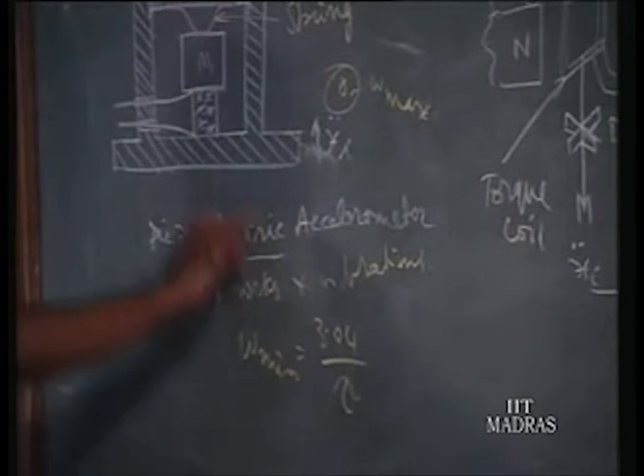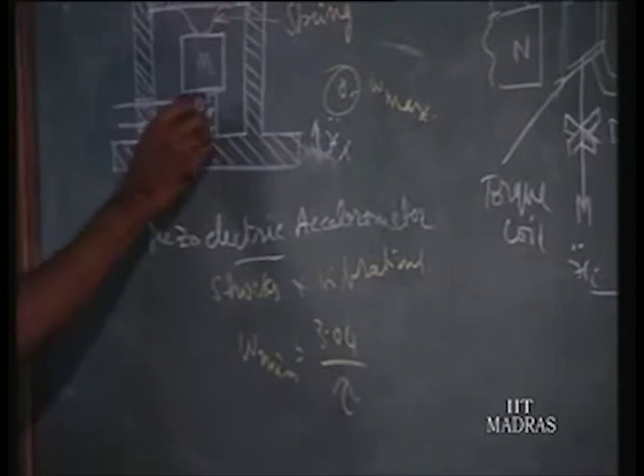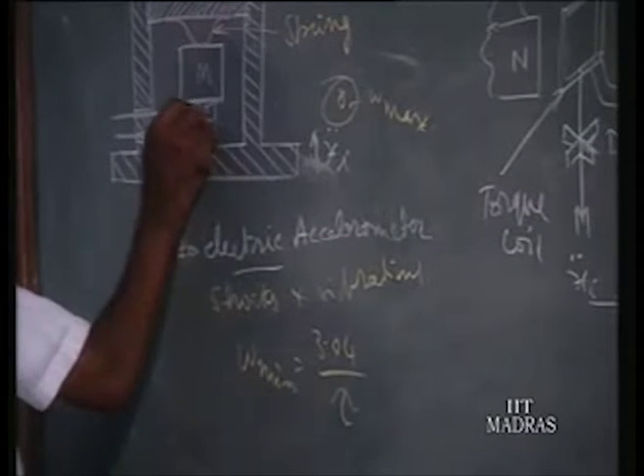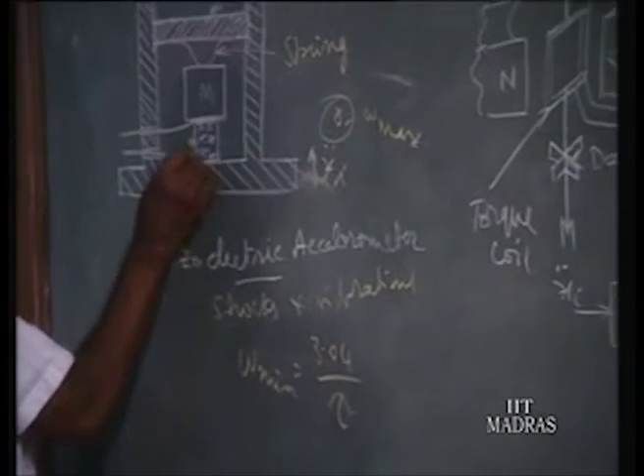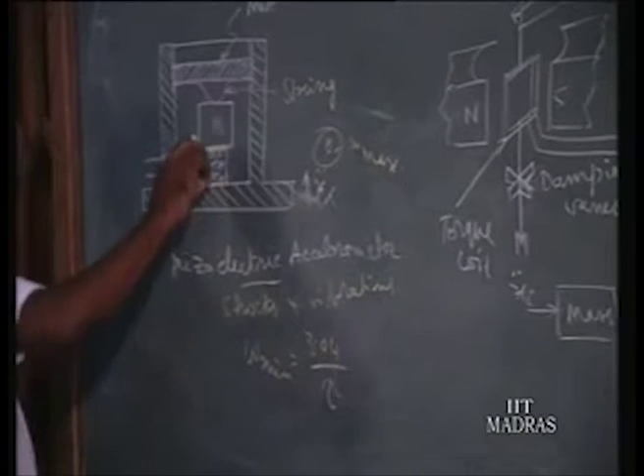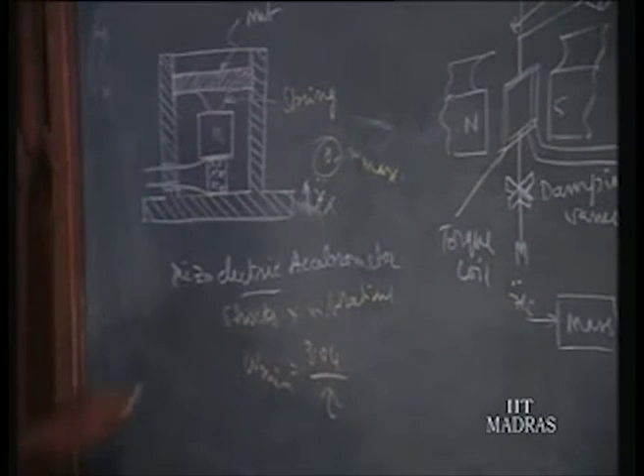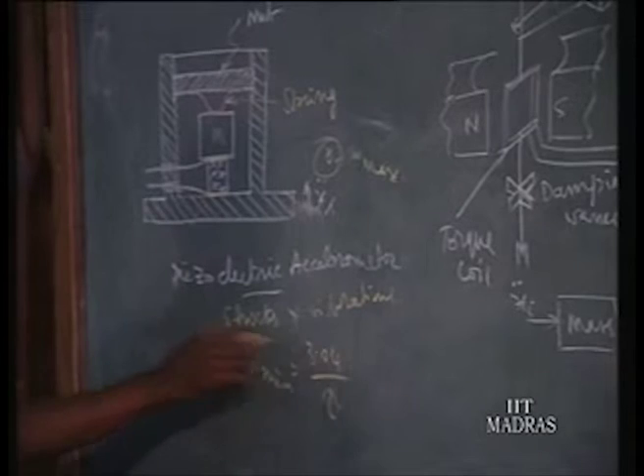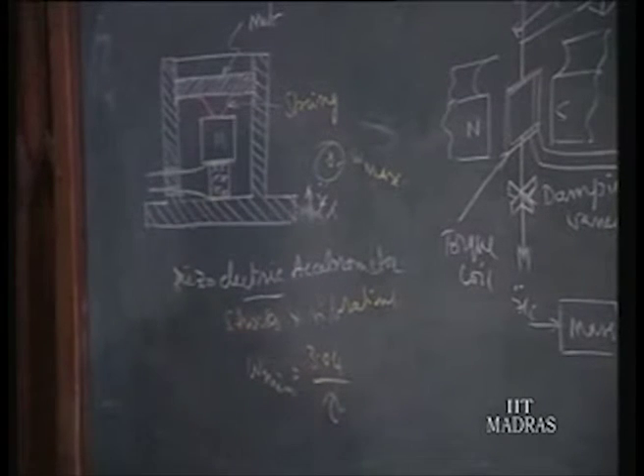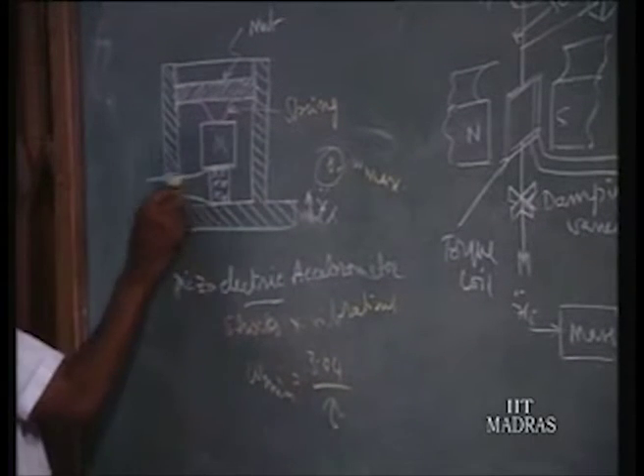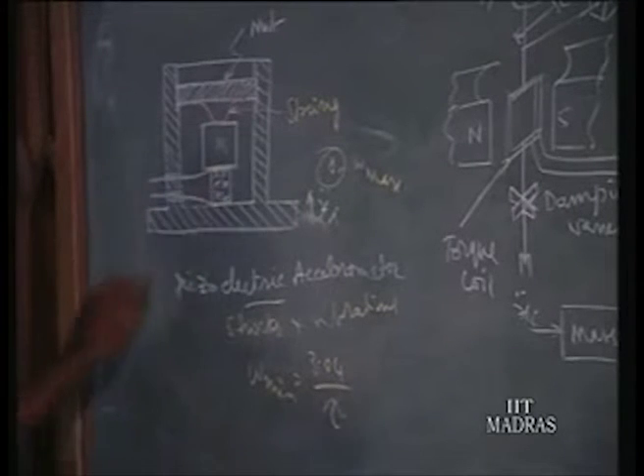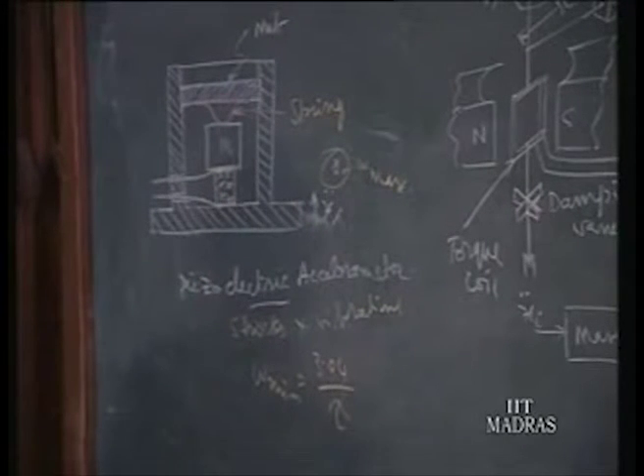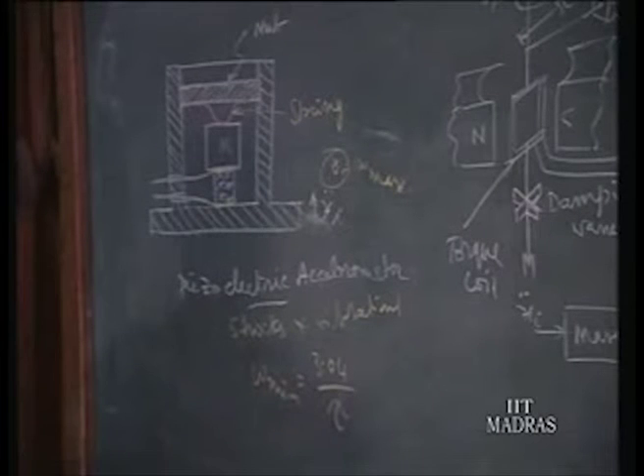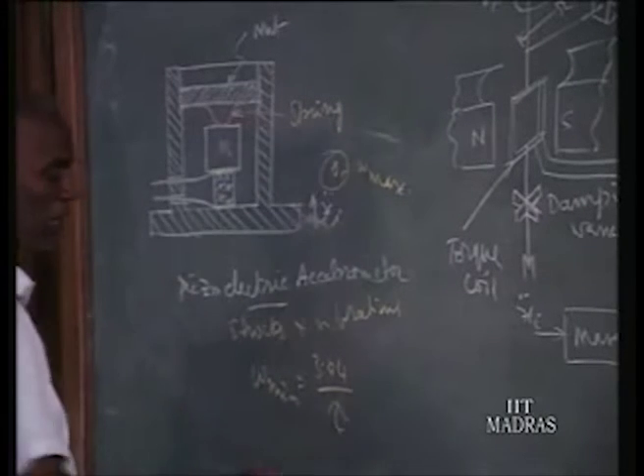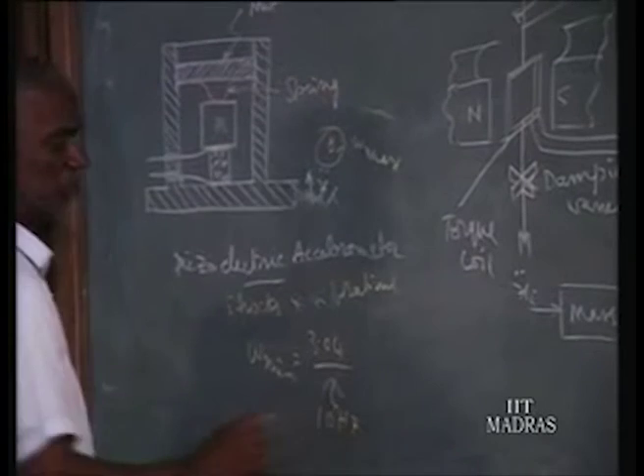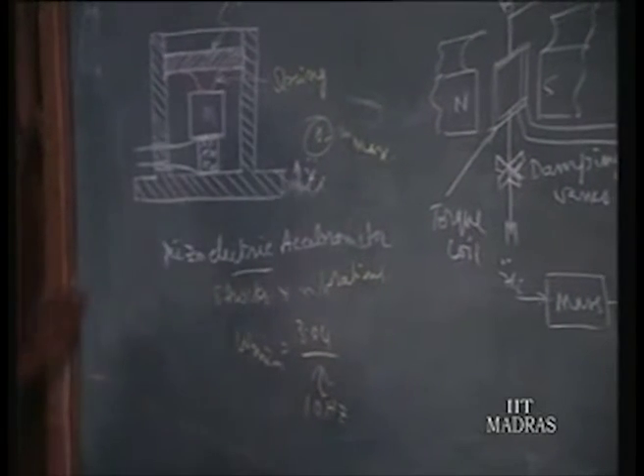The tau is the time constant of that capacitor circuit, or the piezoelectric. We know it has a metallic coating, and from there the charge is taken. In between we have insulating material, so it is a typical capacitor, and the same thing holds good. So omega minimum should be equal to 3.04 over tau, where tau is the time constant of the electronic circuit for this piezoelectric crystal piece. Sometimes omega minimum may be 10 hertz. Below 10 hertz you cannot use this instrument.